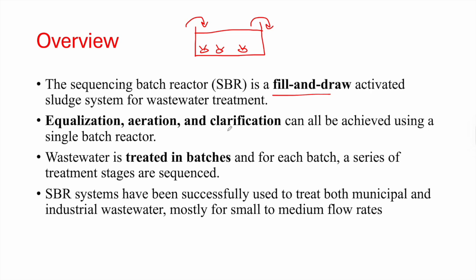Equalization, aeration, and clarification are all achieved within one single batch reactor — one tank for all these processes. The wastewater is treated in batches, and for each batch a series of treatment stages are sequenced. After filling, the full SBR cycle runs, then the treated water is drawn and the tank is refilled with new wastewater.